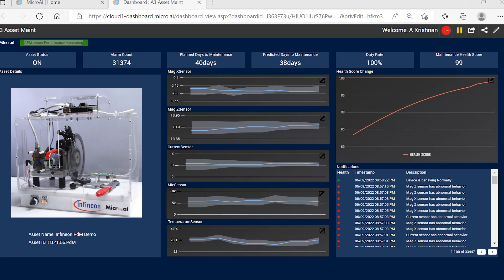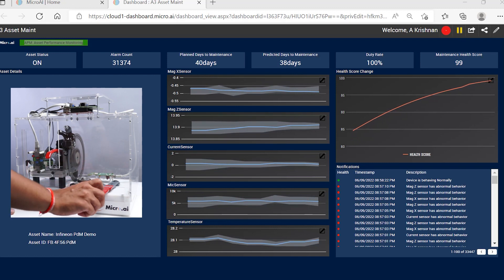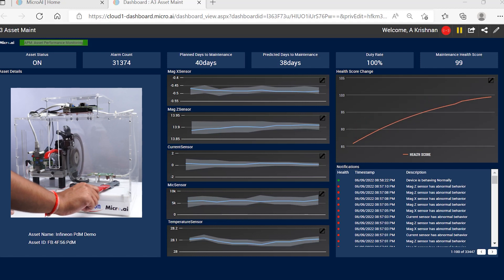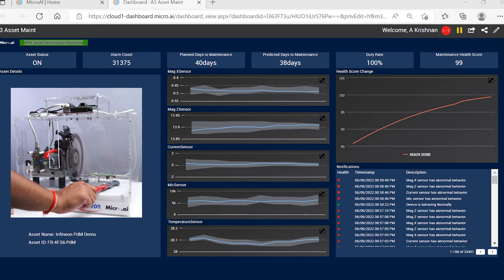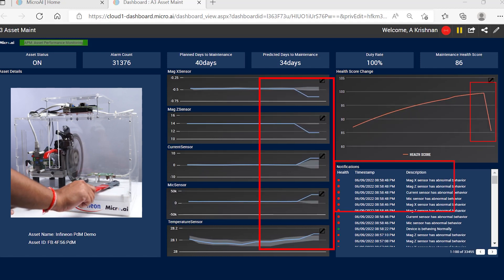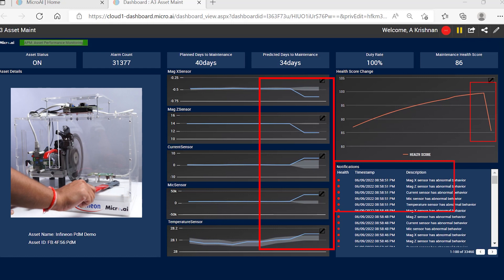To simulate a fault in the system, we have here another braking lever which adds abnormal vibrations, noise, and overcurrent conditions. These anomalous conditions are immediately detected and reported by the local inference engine.